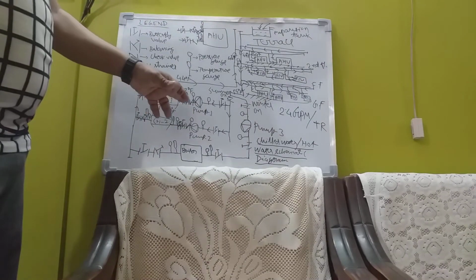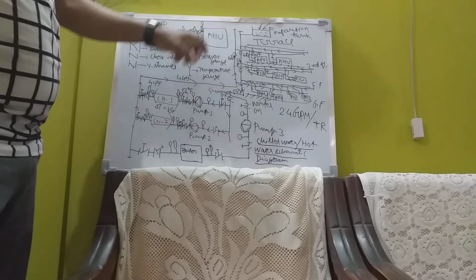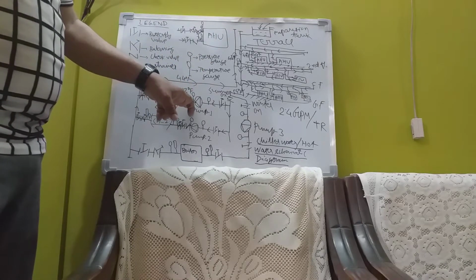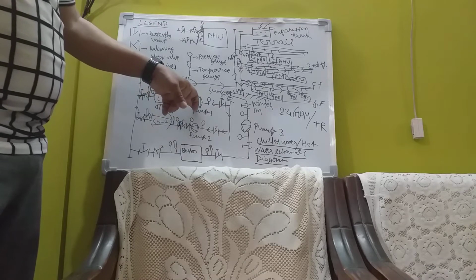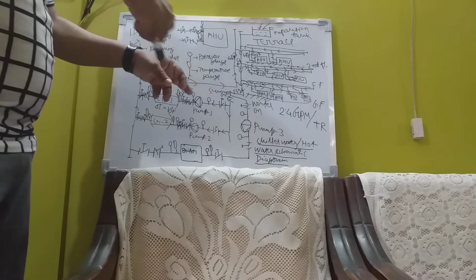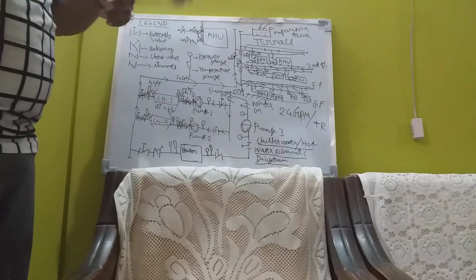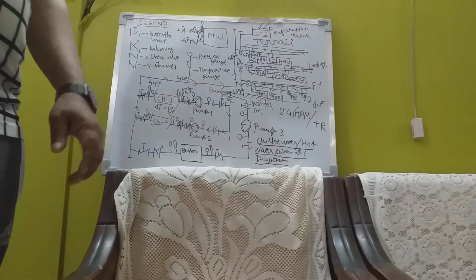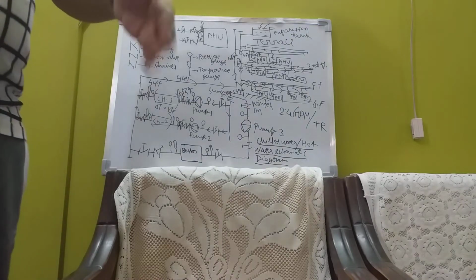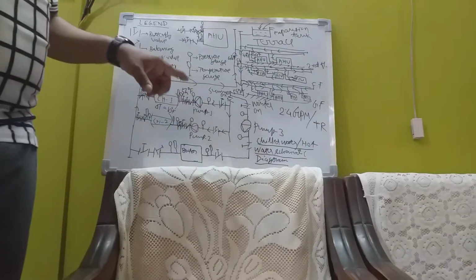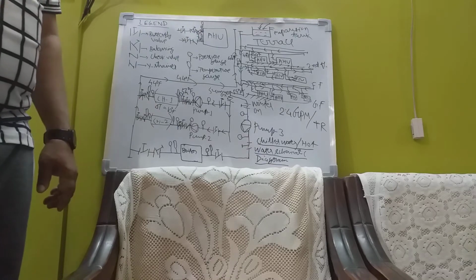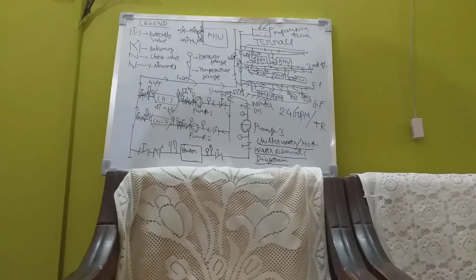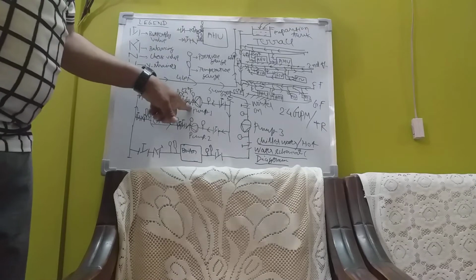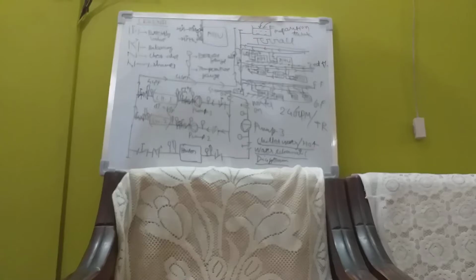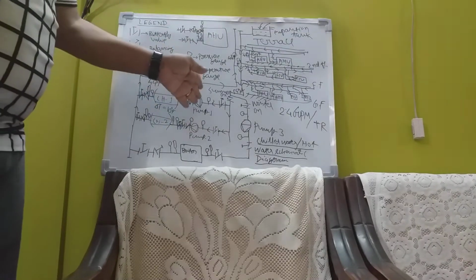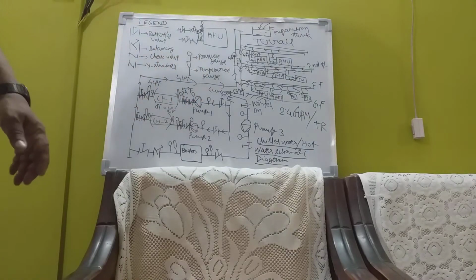The moment, due to some reason, some system fails and water comes back, if there is no check valve, the pump which was rotating in this clockwise direction will suddenly start moving anti-clockwise and the whole pump will burst. Its vanes will break, its casing pressure may come out, its casing may burst out, and as a result there may be a tremendous accident. To stop that, a check valve is provided after the pump. The check valve doesn't allow water to come back to the pump; it's a one-way direction valve only.